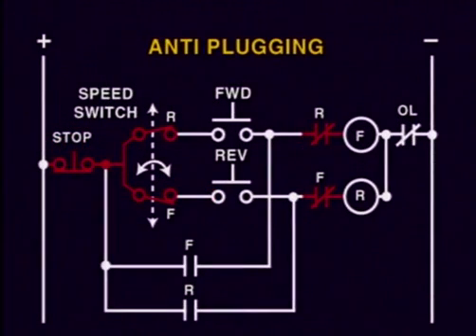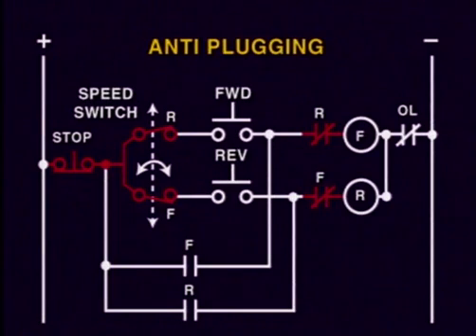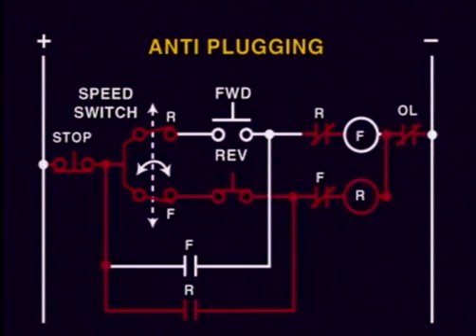A slight variation of the plugging circuit is the anti-plugging. This circuit allows reversal of direction once the rotation slows down to a predetermined speed. If the motor is running in the forward direction and stop is pressed, the reverse will not be allowed until the forward rotation slows enough to close the forward contacts in the switch. At this point, the reverse can take place.